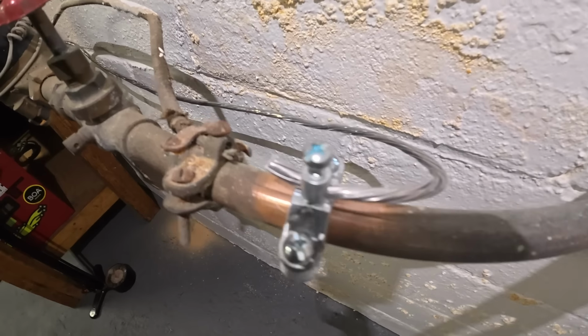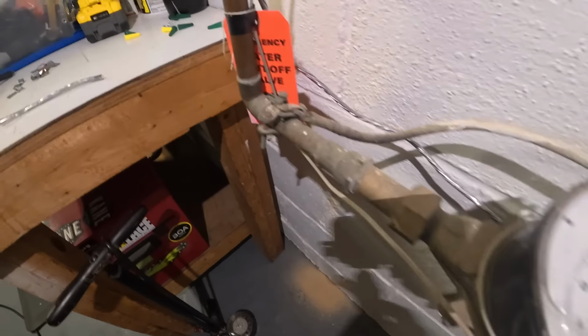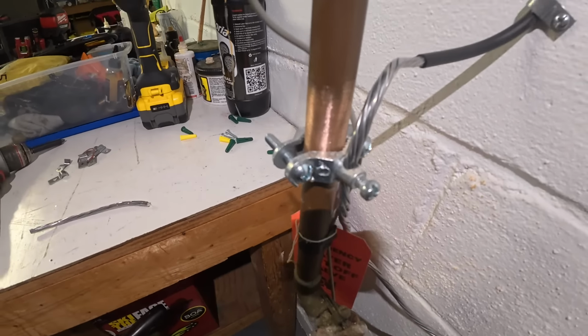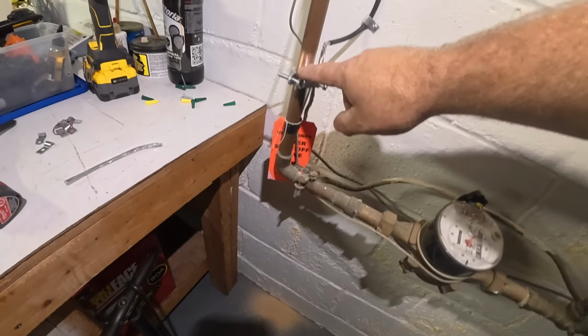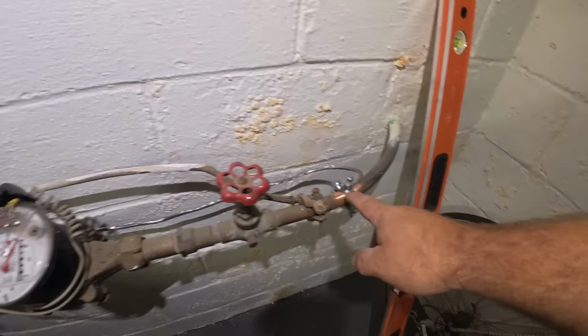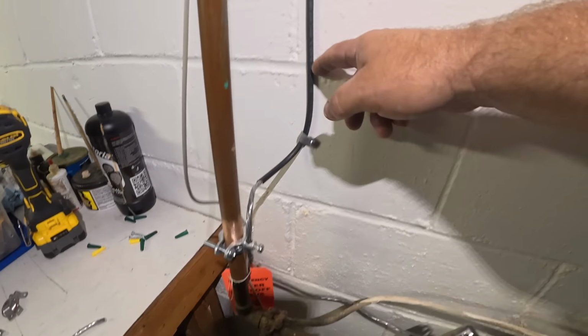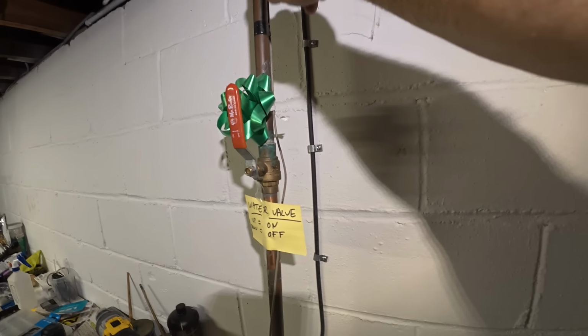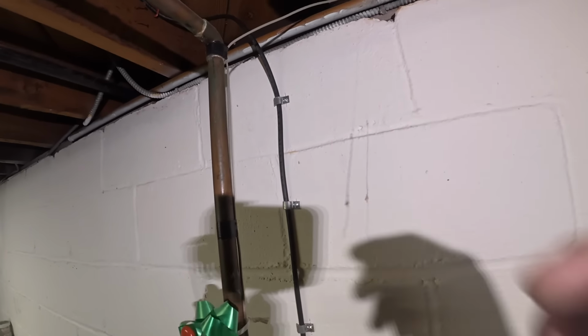Supply side connection across the meter to the customer side. Use the emery cloth to clean up the copper, get a nice contact, strap it up side the wall. Not allowed to strap it to the copper water pipe, that's a violation.